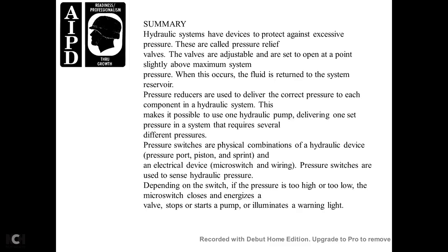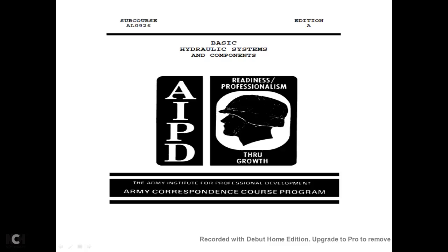Summary — Lesson 3. Hydraulic systems have devices that protect against excess pressure, called pressure relief valves. These valves are adjustable and are set to open slightly above the maximum system pressure, returning fluid to the reservoir when this occurs. The pressure reducer is used to deliver the correct pressure to each component of the hydraulic system, making it possible for one hydraulic pump to supply a system that requires several different pressures. Pressure switches are a combination of hydraulic device, pressure piston or diaphragm, spring, and electrical device (micro-switch) and wiring. Depending on the switch setting, when pressure is too high or too low, the micro-switch closes and starts or stops pumps or illuminates a warning light. This completes the Basic Hydraulic Systems and Components course, AL0926 Edition A, Army Institute of Professional Development.